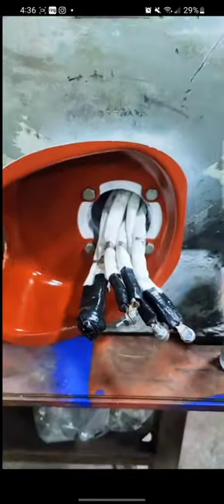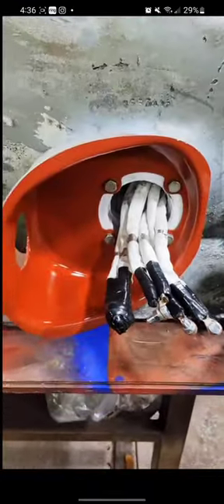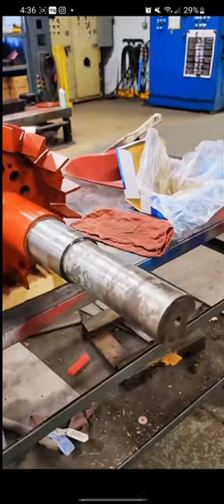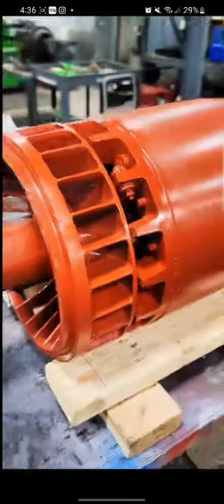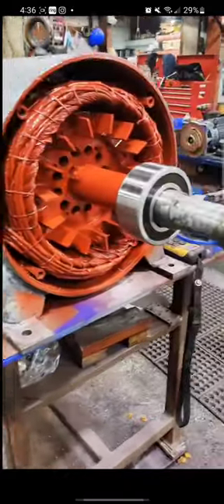Everything about this motor was just in really gross shape. So as we go, we're taking our time on each little piece. There's our final connection inside of that pecker head. Here is our rotor. I'm not really worried about all this gunk on the end of that shaft — we'll clean that up while this thing's rotating. I do love these fans; they look so cool on the rotor.